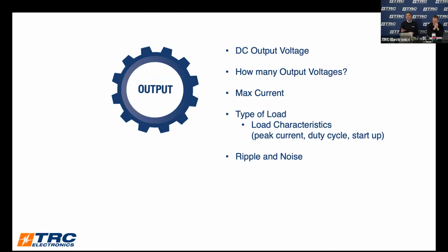Here's some of the things we dive deep into: load characteristics, whether they need a peak current and what the duty cycle of that is. There are some systems out there, especially if you're turning a motor or actuating a relay, that require a peak inrush current that the power supply has to be able to deliver. And if you're not picking the right supply that has that peak capability, you might end up sizing the power supply higher than what you really need.